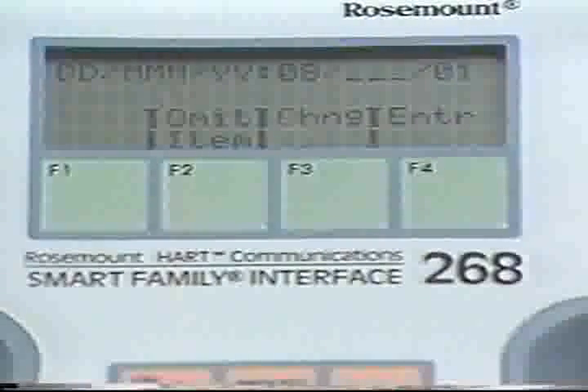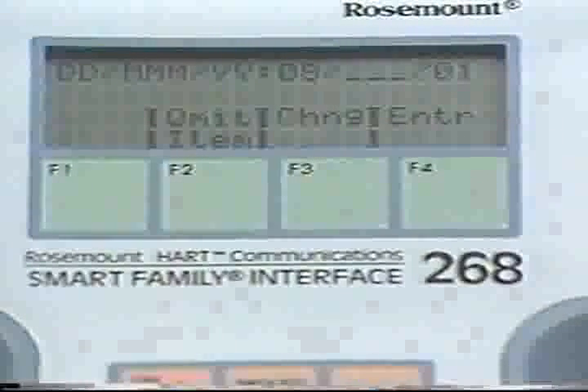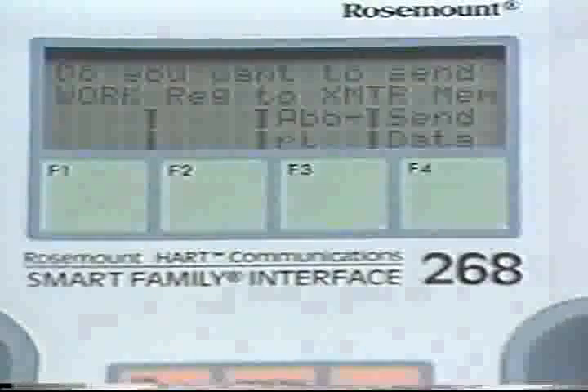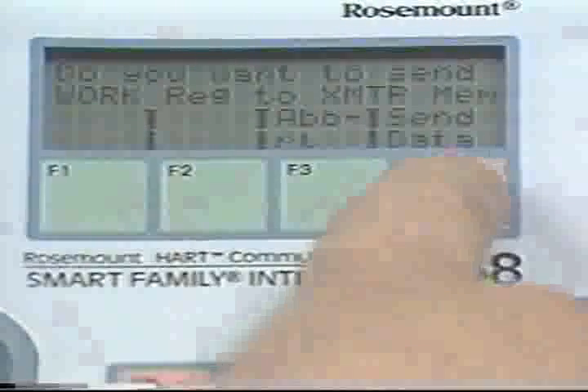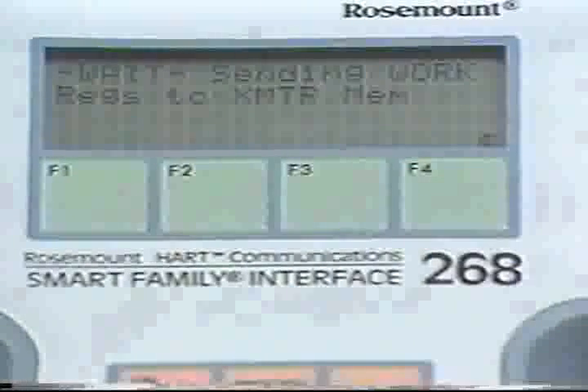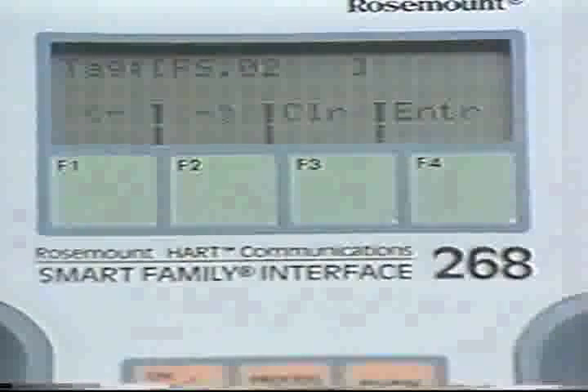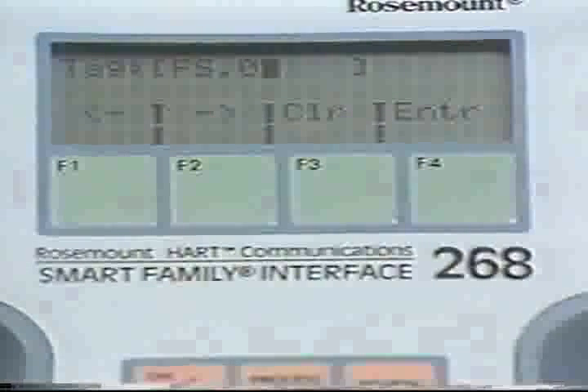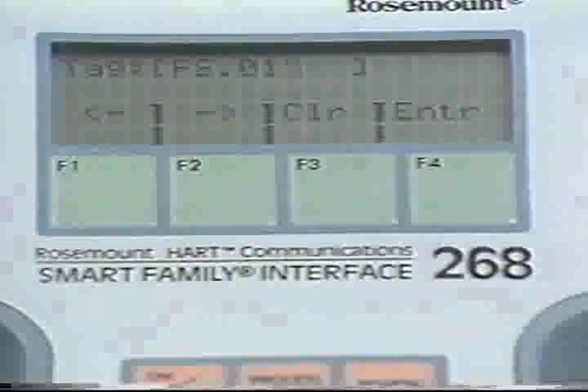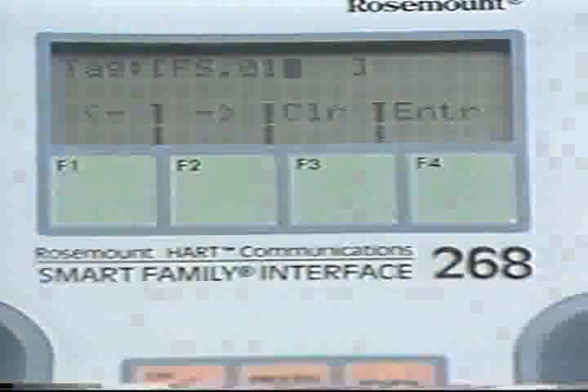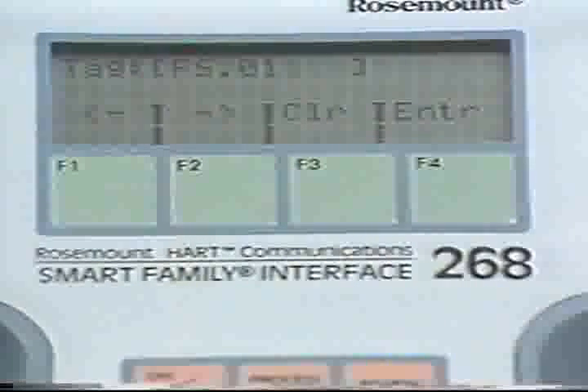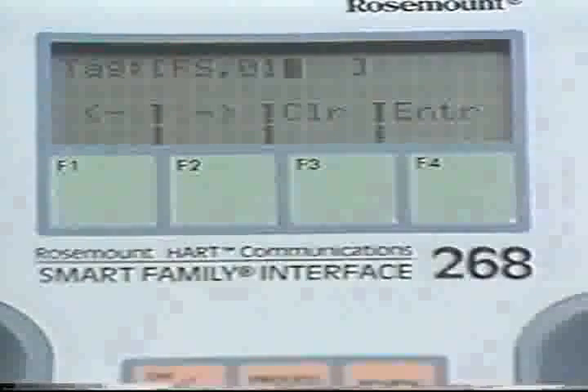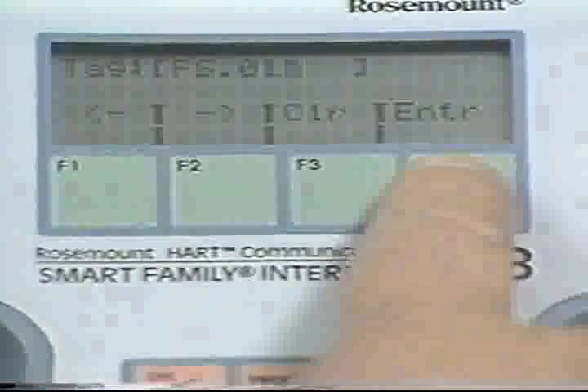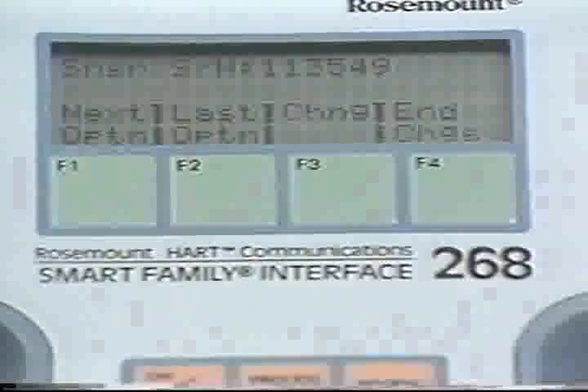At this point, you can change the date to document the configuration. Once you've made any changes, press the key to download the data to the transmitter. Other operating parameters can be adjusted in the same manner. Again, you'll enter the data using the appropriate function and alphanumeric keys and then download it to the transmitter. Once the configuration is complete, the zero and span should be verified.